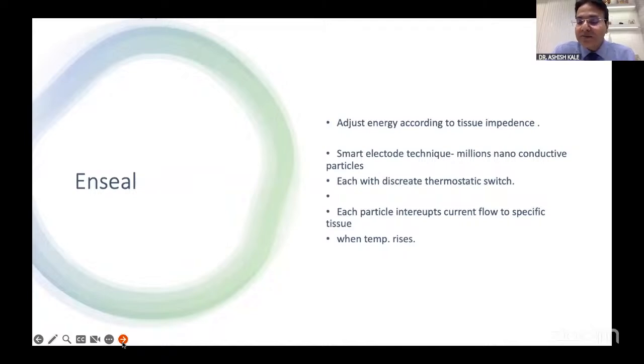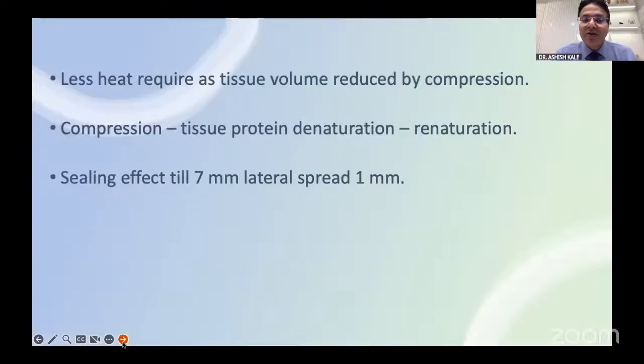Each particle interrupts the current flow to the specific tissue, and when the temperature increases, it causes the coagulation to form. Less heat is required as the tissue volume reduces by compression. Once the tissue is compressed, the volume reduces, and this goes into protein denaturation and renaturation, which causes healing and sealing of the tissue up to 7 millimeters, and it really decreases the lateral spread to 1 millimeter.